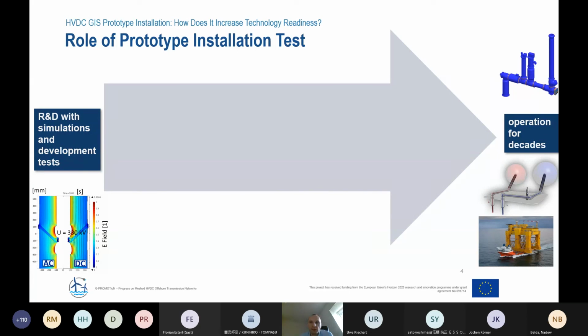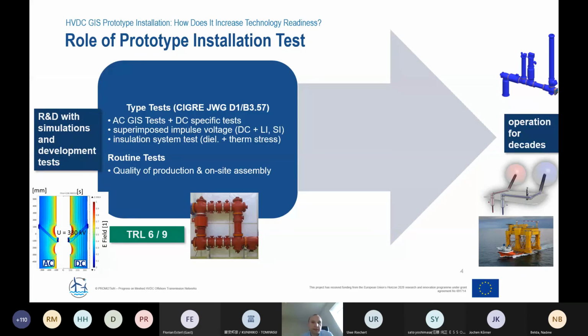And at the end of the R&D, we want to have a reliable product that can be operated for several decades. And what is usually done for an established technology like HVGIS for AC application is we perform all the type tests that are necessary for the product: dielectric, switching, mechanical type tests. And then, once everything is type tested, we also perform the project-specific routine tests to ensure the quality of production in the factory, but also to verify that on-site, on the project side, everything is assembled correctly.